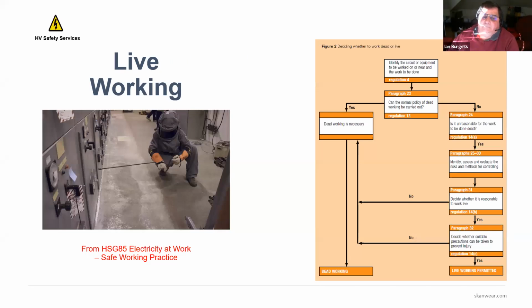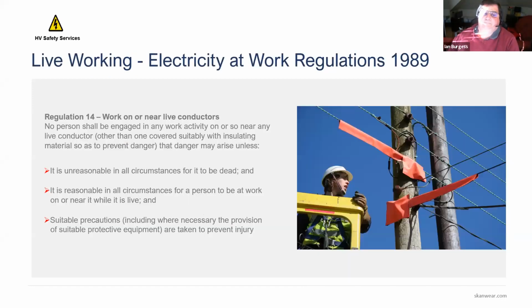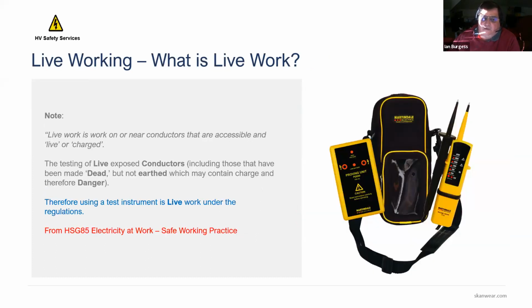So we come on to live working. Now, again, there is a lovely flowchart for this that helps to identify where it is, and that's really useful in the book. But we accept in the UK that live working will need to be done. And I'll be very surprised if there isn't anyone who hasn't done live working in the UK. But the regulations say no person should be engaged in any work activity on or near any live conductor where danger may arise, unless it's unreasonable in all the circumstances for it to be dead, it is reasonable in all circumstances for a person to be at work on or near it while it's live, and suitable precautions, including when necessary protective equipment, are taken to prevent injury. That is the law. If you can't meet one of those three, then you can't do it live. No argument. That's the way it is.